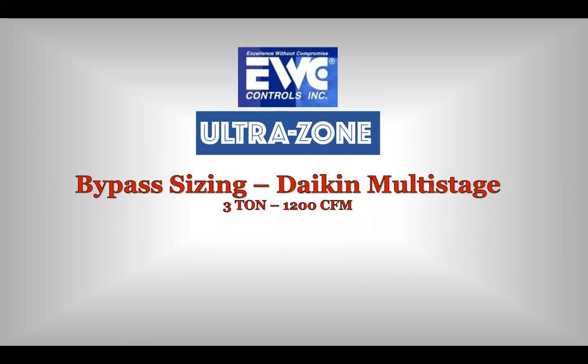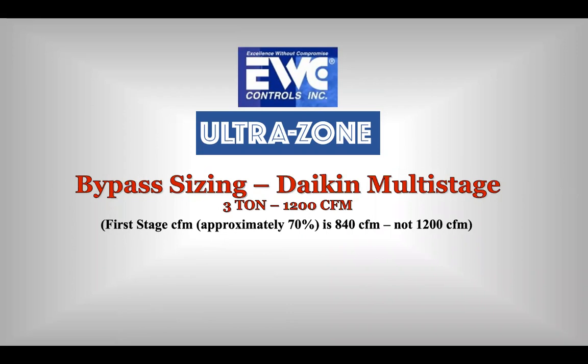Let's look at the multi-stage. A little different consideration here. First of all, I'm able to use first stage CFM because my UT3000 will satisfy any one of those zones in a normal operation without calling for second stage. That means I can now look at first stage only.